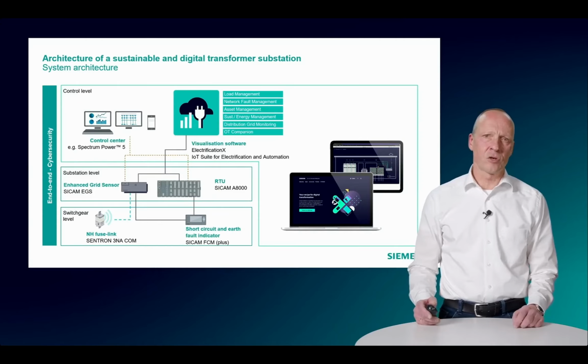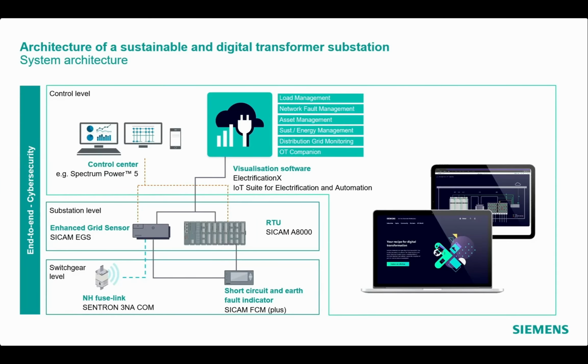The next slide shows the overall system architecture from the sensor to the cloud of a digital transformer substation. On the switchgear level, we have the smart fuses on the low voltage and the C-bushing with SICAM FCM Plus or external LPITs with CCAM FCM on the medium voltage side. A connection to SCADA via IEC 61850 or IEC 60870-5-104 and to the cloud via MQTT is established by means of a gateway, which could be either the SICAM EGS or the SICAM A8000.